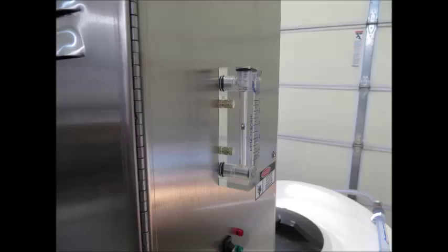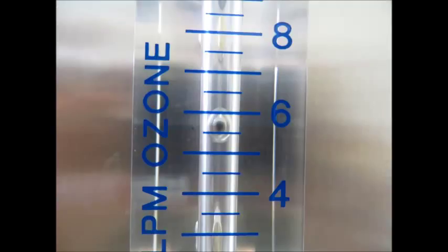That's really all there is to it. The key is to make sure the pull of the venturi equals the push from the oxygen concentrator. They should be balanced.